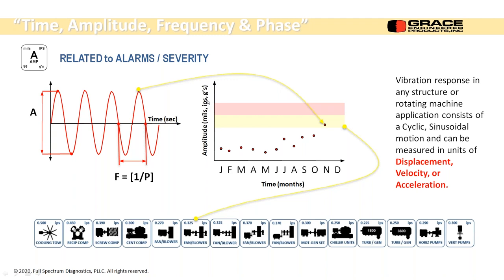So here we're using velocity. That's where my alarm line is. Okay, and we'll start trending. Once we know the machine, we know a rough estimate of what the alarm levels are going to be. Now these are much more meaningful.